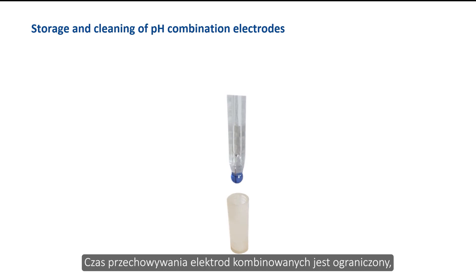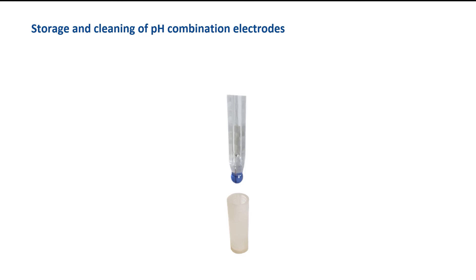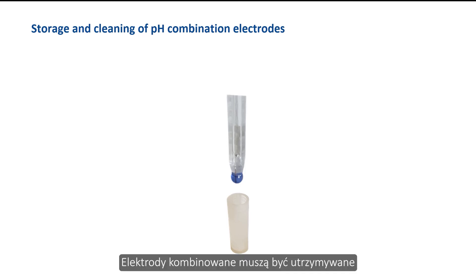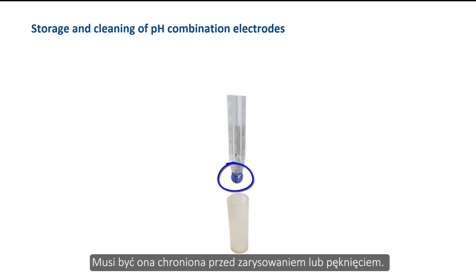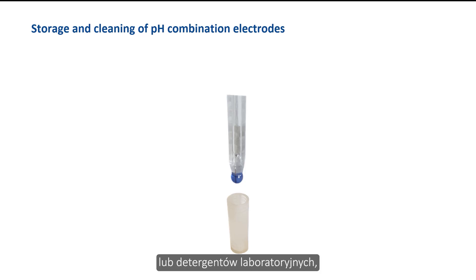The storage time of combination electrodes is limited; it is recommended to use them within 6 months at the latest. The electrodes are stored in a wet retaining cap filled with potassium chloride and must not dry out. Combination electrodes must be kept clean over their lifetime. The electrodes as a whole are quite stable, but the glass membrane is sensitive and must be protected from scratching or breakage. Cleaning can be done with water, or with glass cleaners and laboratory detergents such as alcohol or acetone if required.